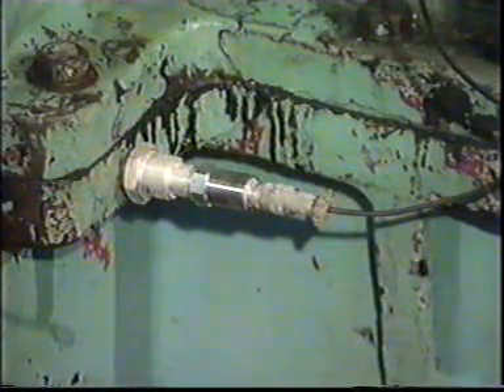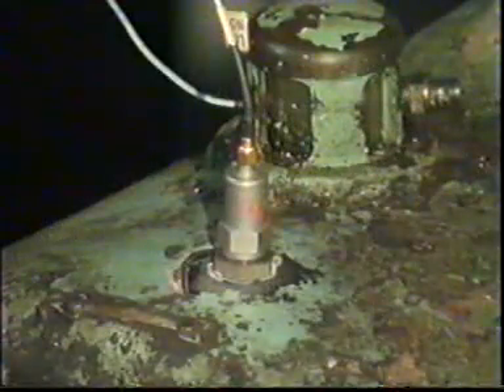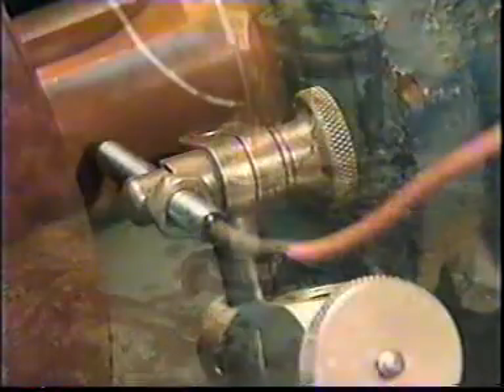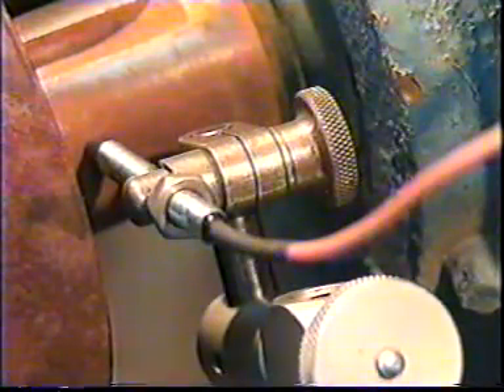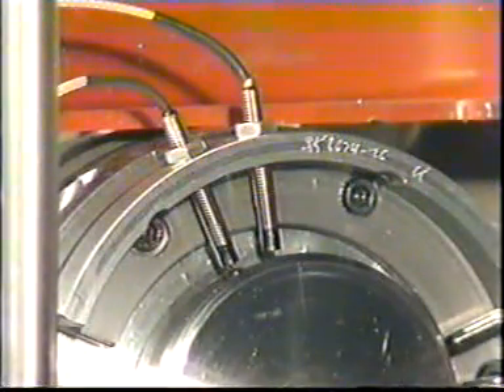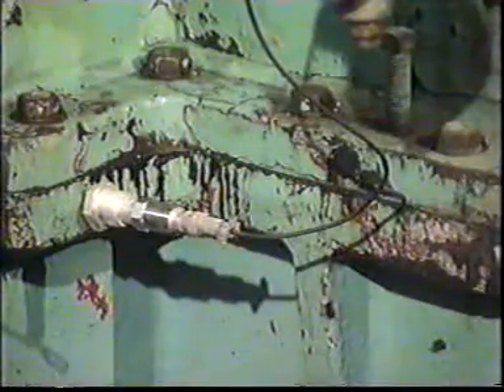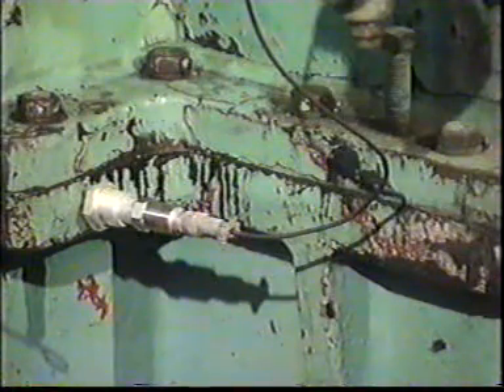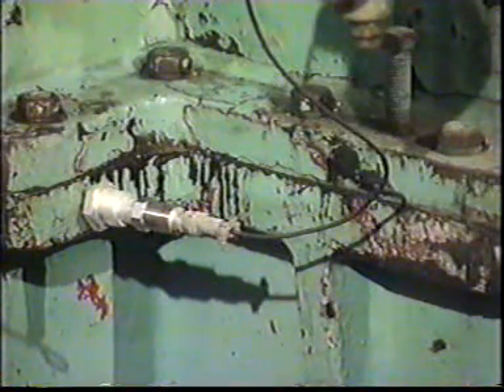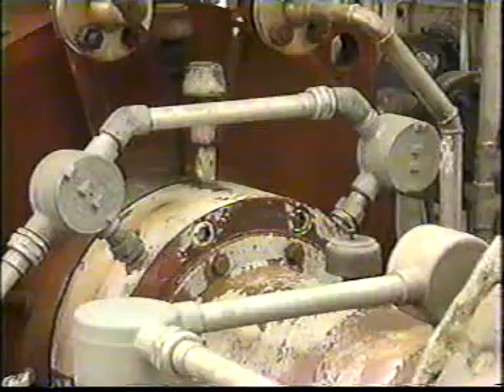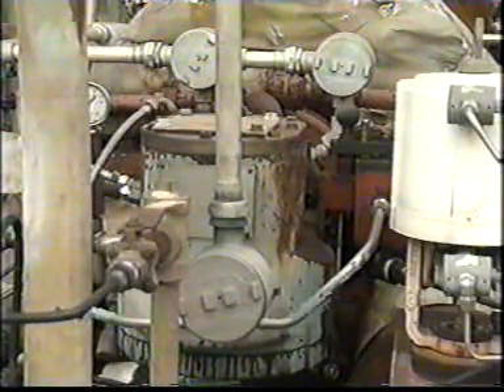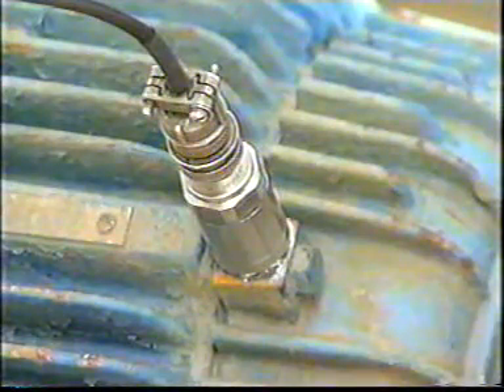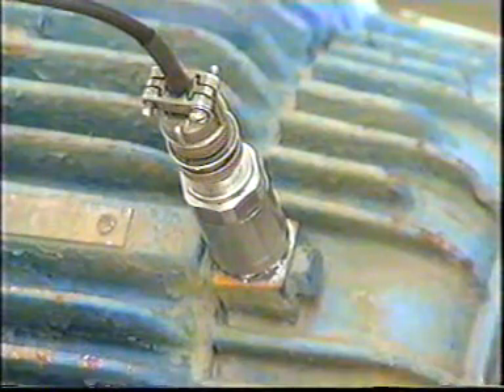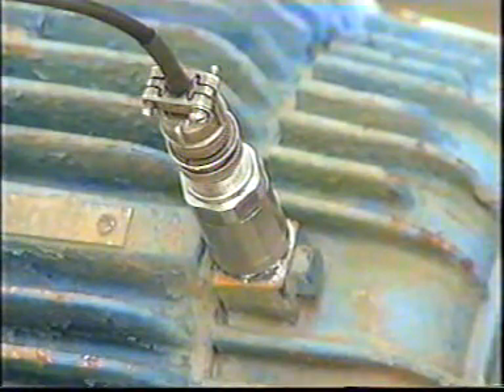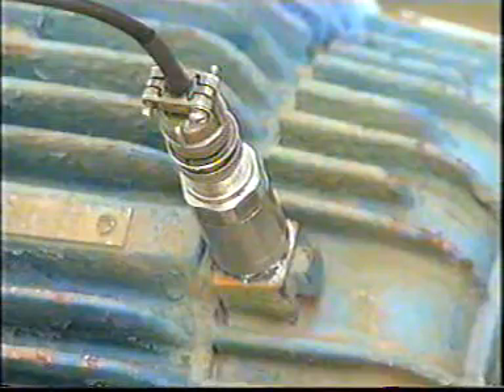Sensor orientation is crucial to proper vibration monitoring and analysis. Improper placement or orientation could result in missing some vibration problems. There are three basic sensor mounting geometries: single position, two position, and three position. A single position monitor typically measures vibration amplitude, component displacement, or component position.